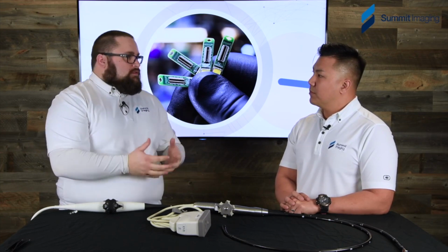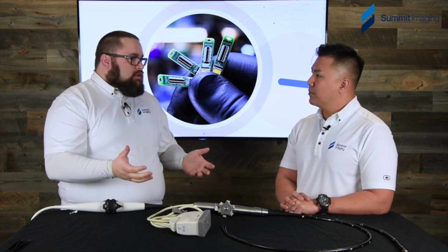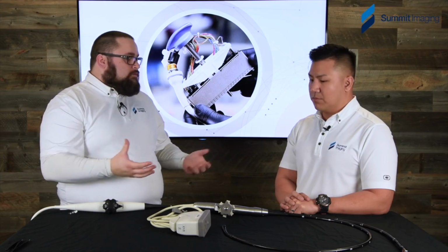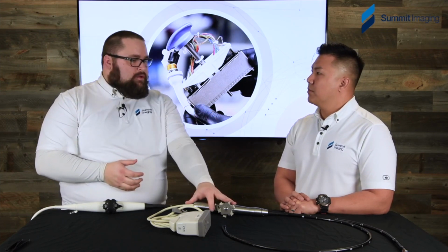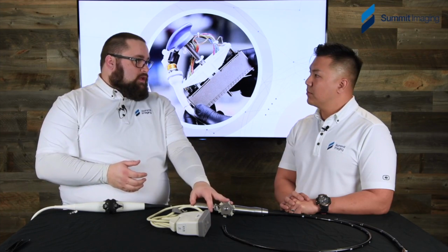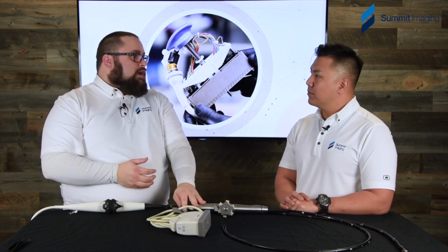And then, what's the life of the transducer look like? Now this could be downstairs too with the biomed shop. It could be with the OR manager, but this information should be easy to find. And we should know what's happening with this transducer next and where it's been. Most importantly, if it's failed leakage, where's it going to now? Is it going to go to biomed for another checkup, make sure that leakage test failure was accurate, or is it going to go straight out to a vendor like Summit Imaging to get evaluated as fast as possible?